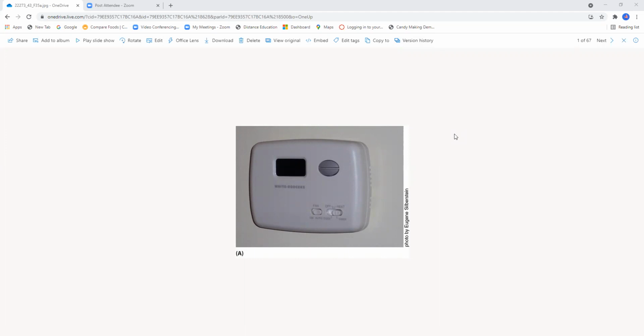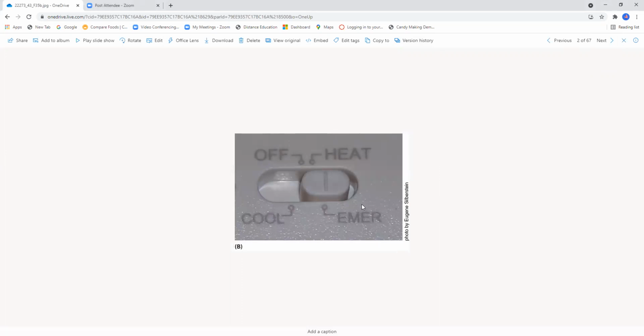Okay, this is a thermostat, basically for a heat pump system. Notice here on this heat pump thermostat, we have an off, a cool position, a heating position, and emergency heat. On all heat pump thermostats, whether they be mechanical or digital, they have a function switch that the homeowner can switch to emergency heat in the event that the heat pump does not operate correctly in its normal mode.